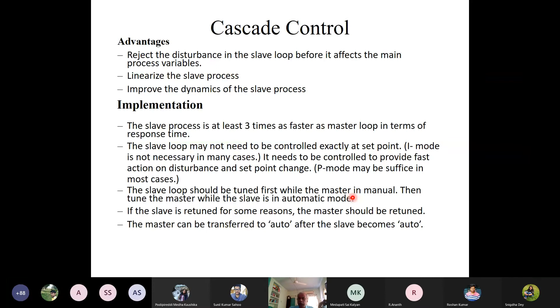So in actual practice, normally we put all the control loops in manual, both the master controller and the slave controller. We tune the slave controller first. Normally we use a proportional controller and tune the slave controller. Then we put it in auto. Then we tune the cascade primary controller or master controller, and then we put the master controller in auto mode.